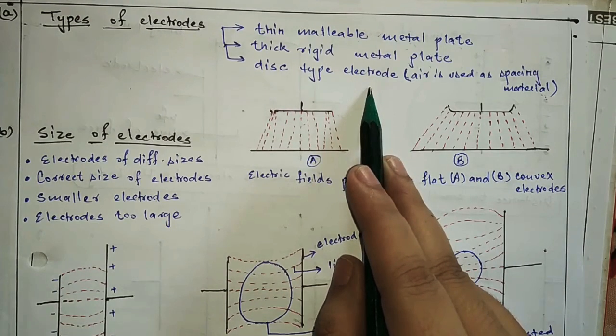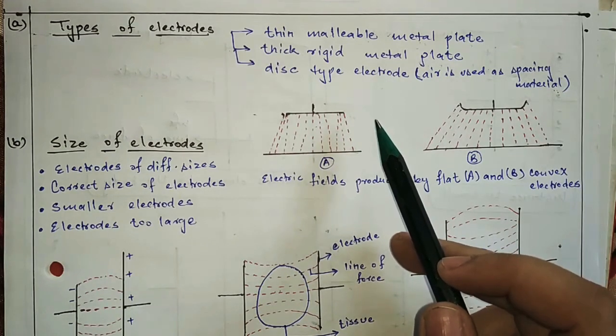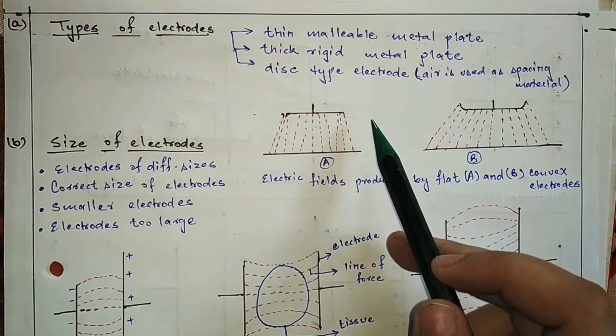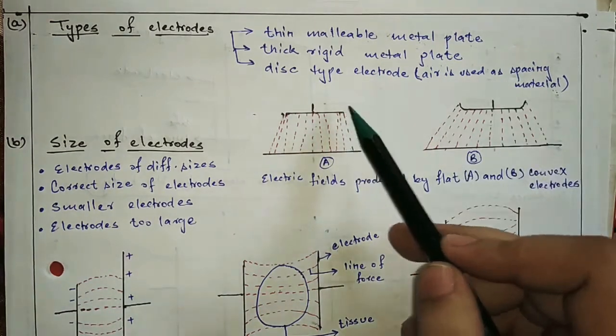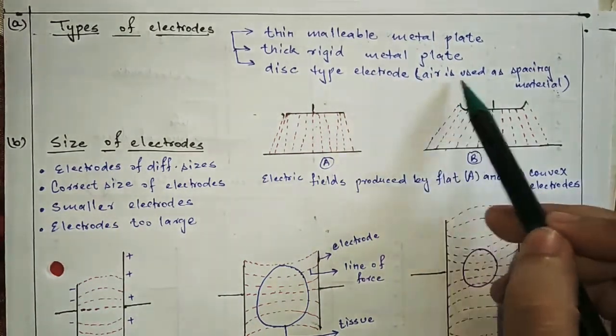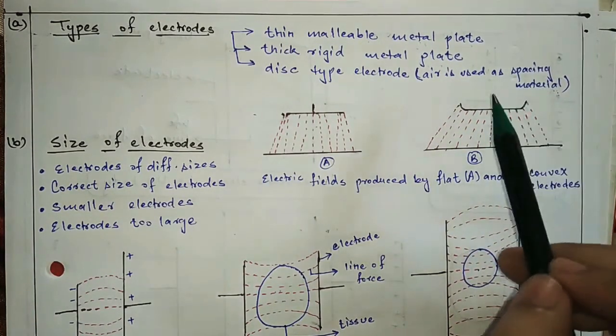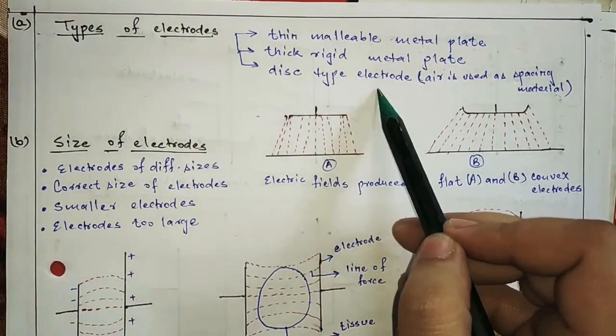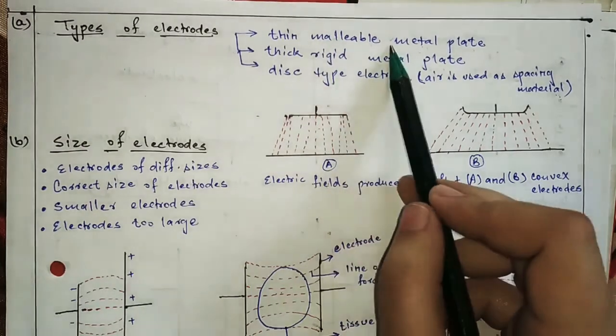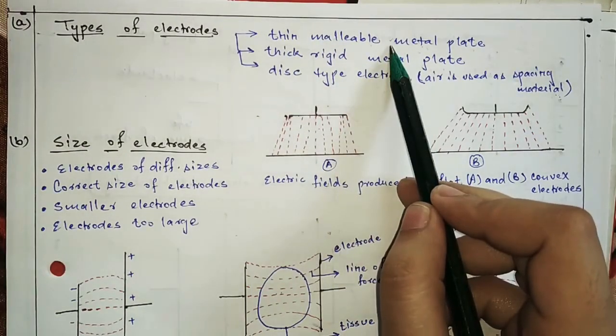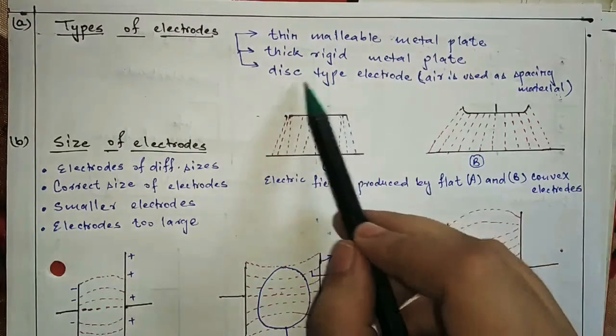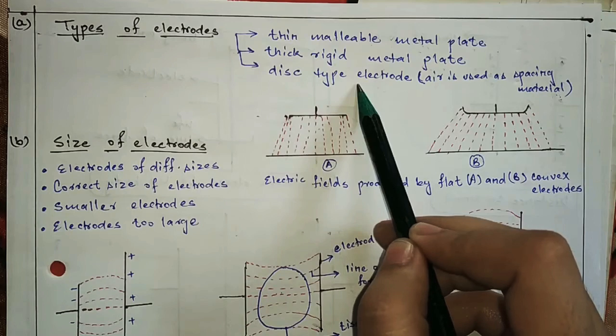Next is the disc type electrode. This disc-shaped, circular electrode has no direct contact with the skin. Between the skin and the electrode, air works as a spacing and insulating material. The disc type electrode is also covered with transparent plastic.